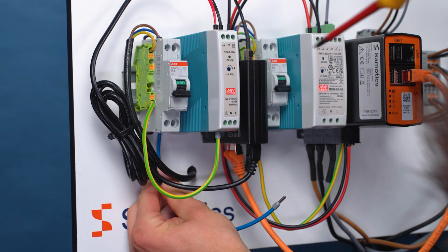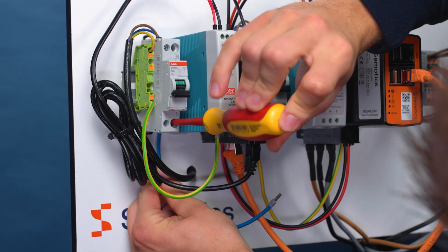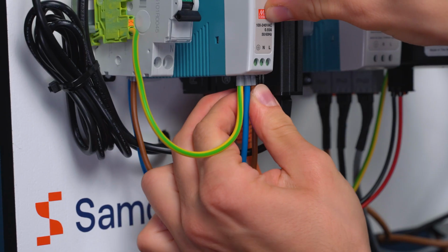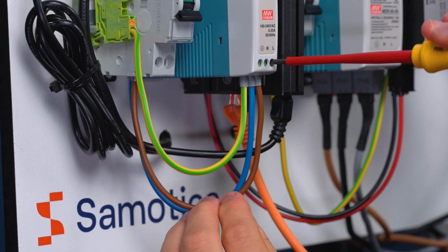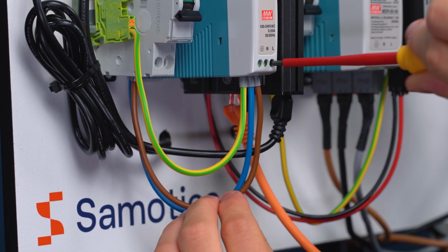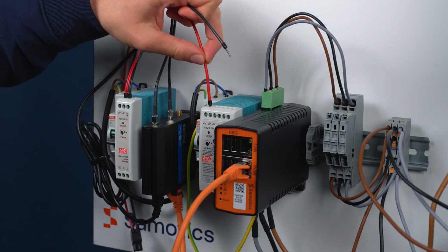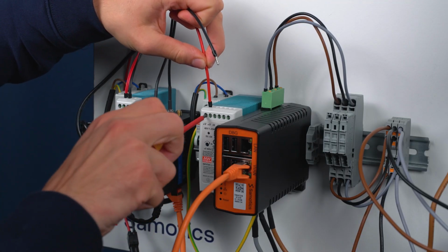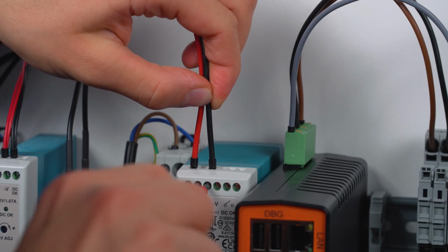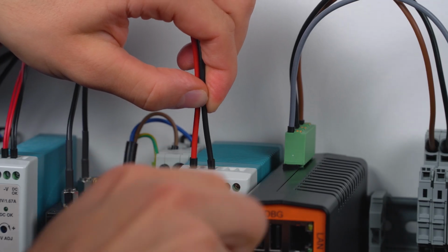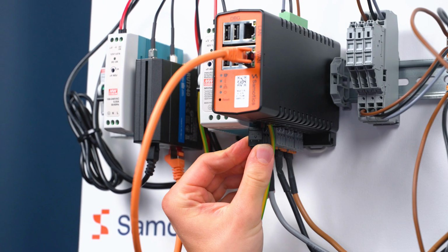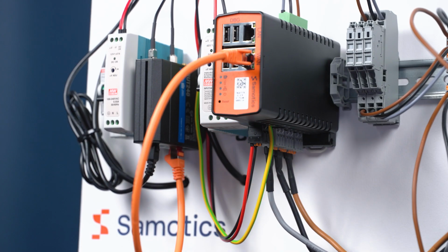All NOVAQ units require a 48-volt power supply. Connect each provided power supply to the grid voltage through a circuit breaker. Then attach the red-black wire to the power supply's terminals, ensuring correct polarity. Plug the black connector into the bottom port of the corresponding NOVAQ.